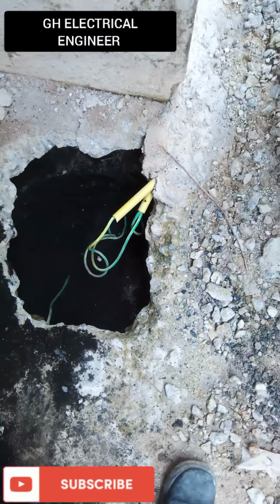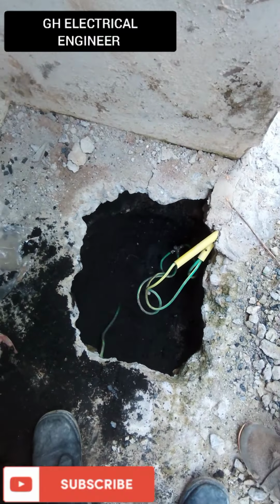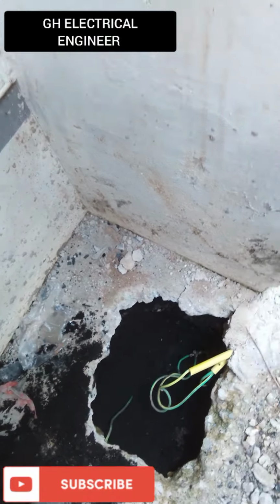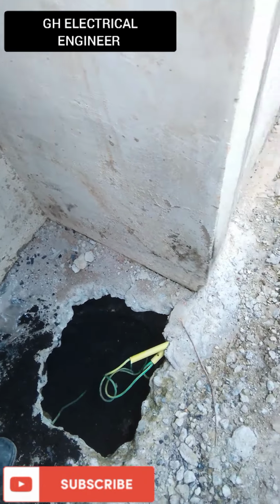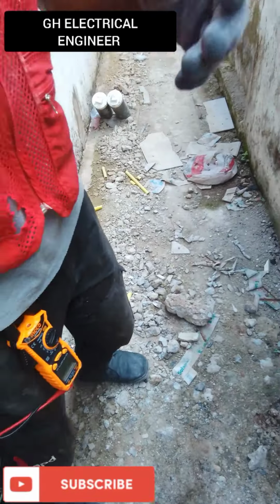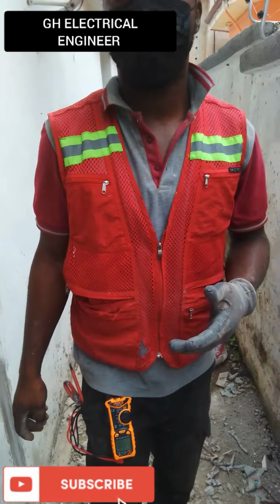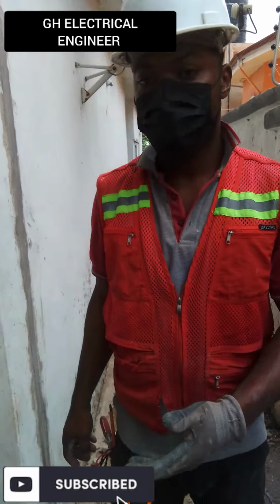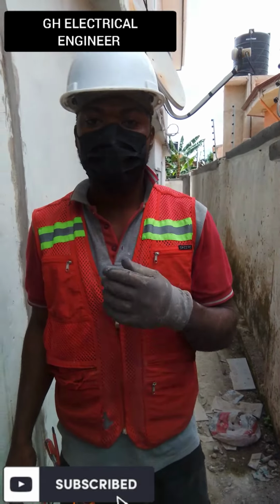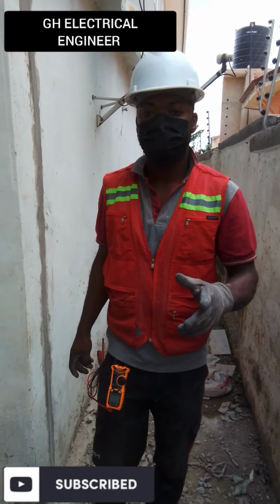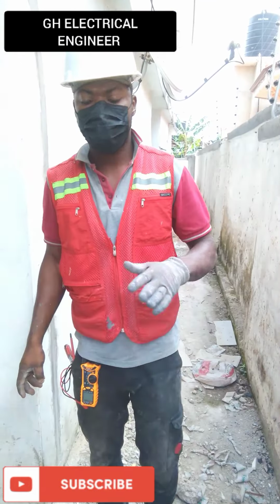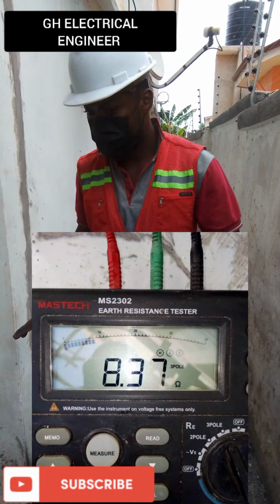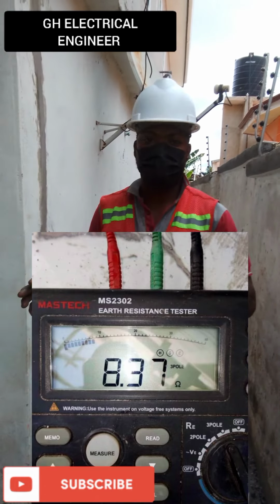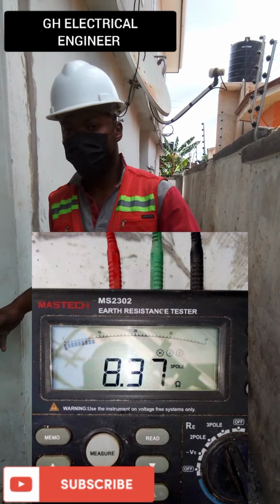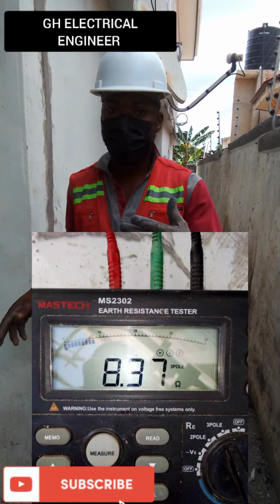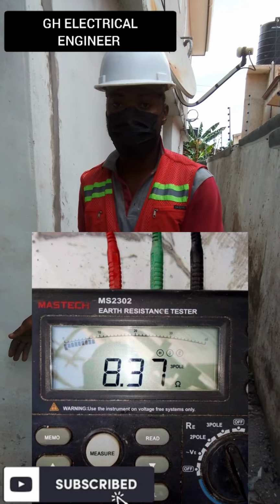The first thing is I was so annoyed when we couldn't get the earthing, because when you bury another rod, definitely the client is not going to pay for that. But if we are engineers, we have to pay. Whether we like it or not, we have to provide another earth rod. So when we buried one earth rod, nothing worked. We had a high resistance, almost 8.37 ohms. That is what you can see on your screen.